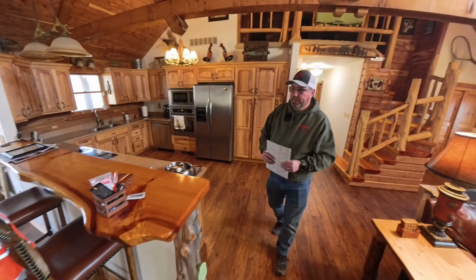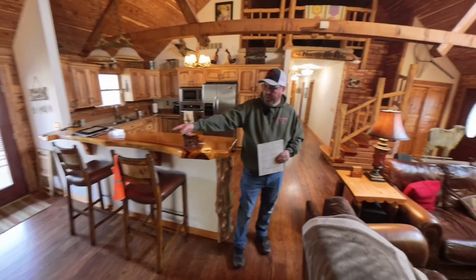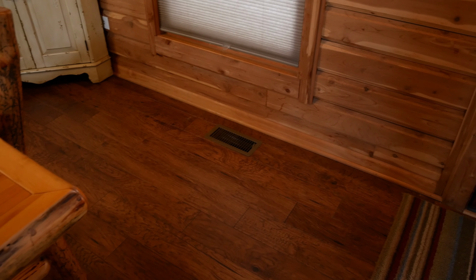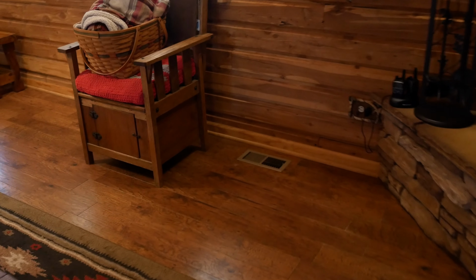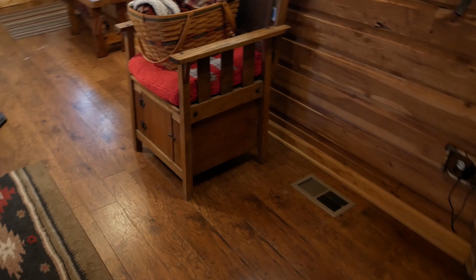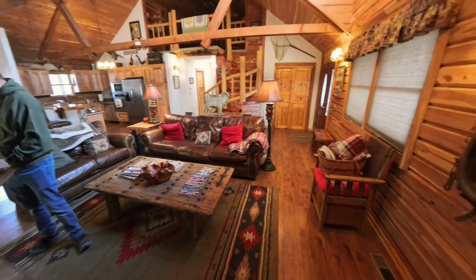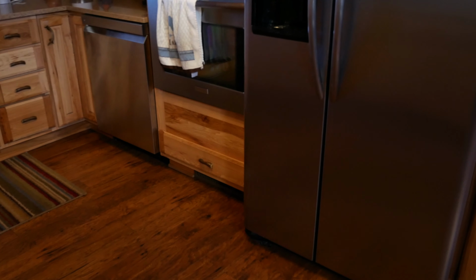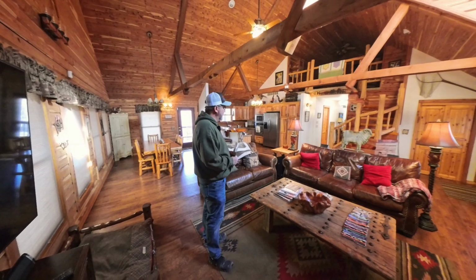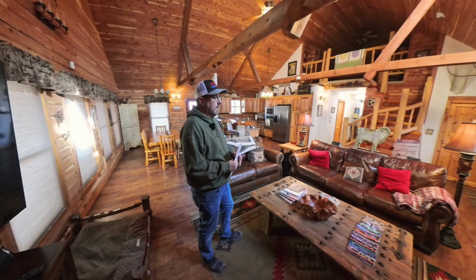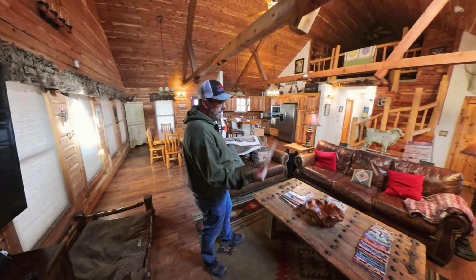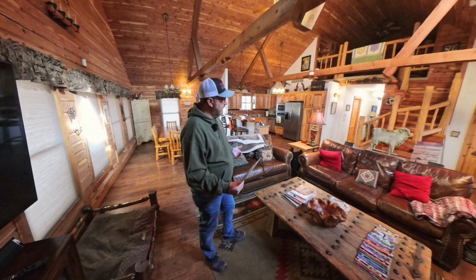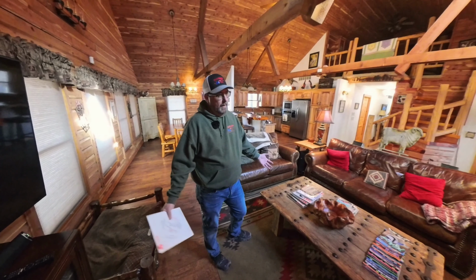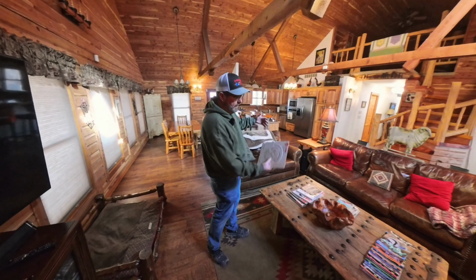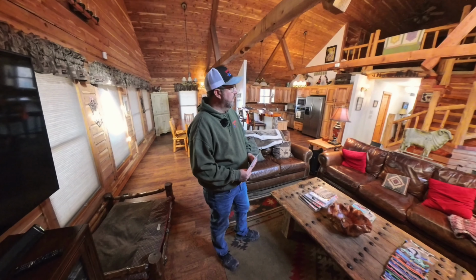We also added 2 supply registers, one over here by the back door and one opposite end of the room on that outside wall to add more supply air to this area. Initially, it only had 1, 2, 3, and it had 1 kick plate under the cabinets over there in the kitchen. This room was hot in the summertime, cold in the wintertime, so we're not only supplying more air to the space now, we've added more return so that when air comes into a room, it has enough return to circulate across the room and condition the big room.